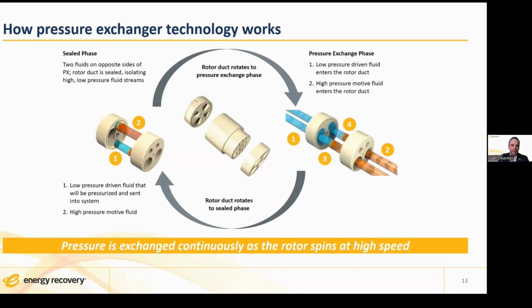And in the other pipe, we have the low pressure feed that is pressurized and moved by the high pressure brine. Then it spins to the sealed phase, and we have again the low pressure feed, the high pressure, low pressure brine depressurized, and the high pressure feed, the low pressure feed prepared to be again to pressure exchange. As the rotor is continuously spinning, it is done continuously without the use of any valve and without any losses.